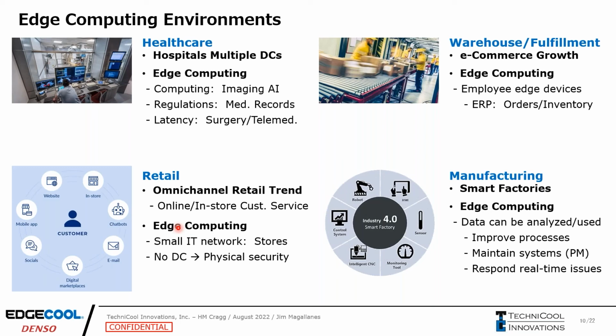All this needs IT equipment at each store, and a lot of times there's no specific data center room within these stores. Maybe they're doing a mixed room, so they have a break room with their IT equipment within that room, and that needs to have some type of security. So you're putting the IT equipment plus the cooling, the UPS, everything behind a locked server rack, and that helps with just human errors. Maybe something goes down because somebody hits a button or pulls out a wire or something like that. That's really key.